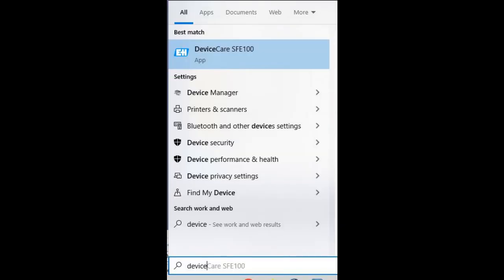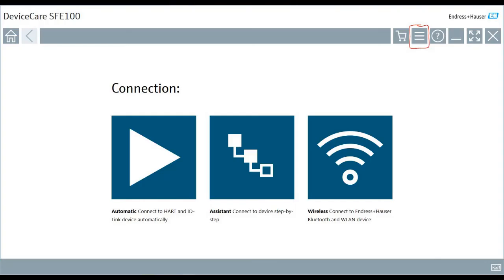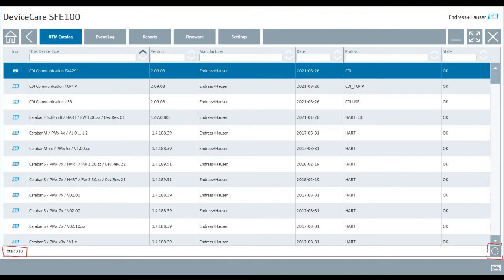Now that you have Device Care installed, we're going to want to open it up. Go to your start menu, open Device Care. Device Care should open. Now that it's open, the first thing we're going to need to do is make sure that our DTM catalog is updated. Click on the hamburger icon on the top right corner. This will open up the DTM catalog. And in the bottom left corner, it will show you the total DTMs that have been installed, depending on if it updated when you opened it or how many DTMs that you've installed out of the packages.